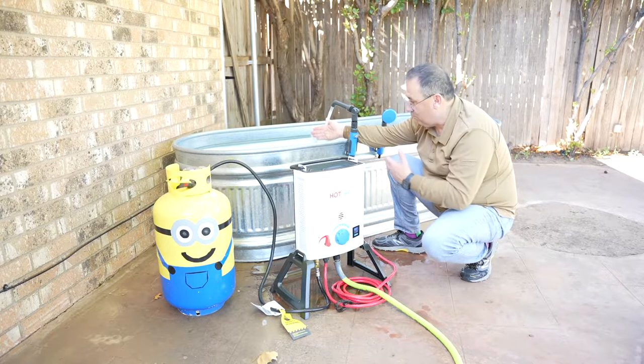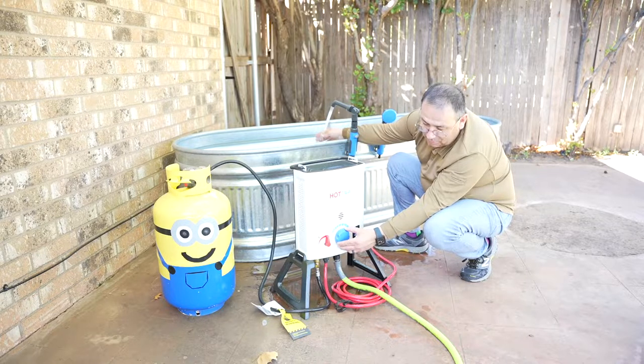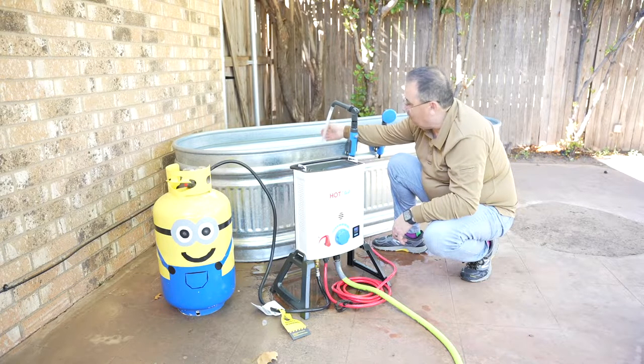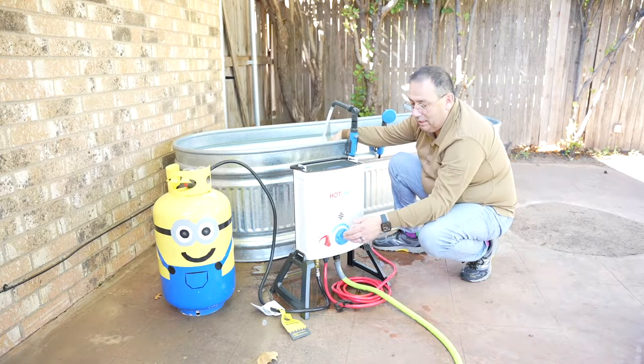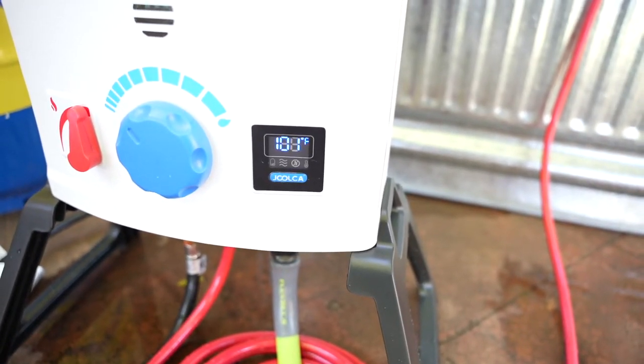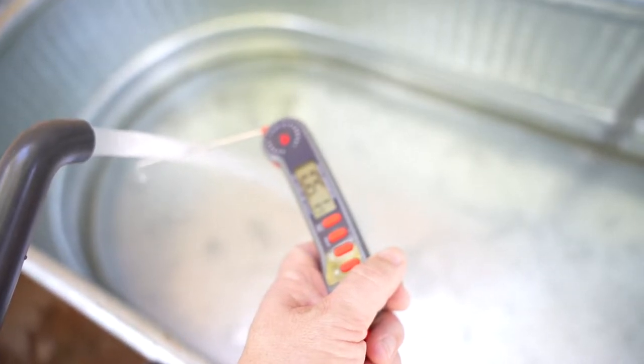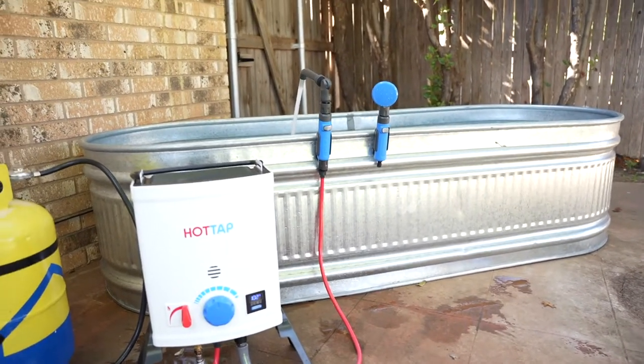That would be a very comfortable shower — it's not scalding. If I slow the water going through the system, yeah, that's definitely hot — I can't keep my hand over it. Let's get a temperature probe. You can see the temperature rising pretty quickly: 98, 99, over 100 already. At the faucet I'm reading 104 to 105 degrees — definitely a nice warm shower.